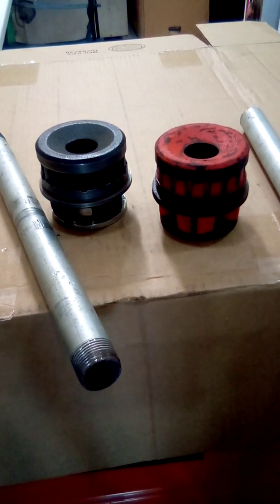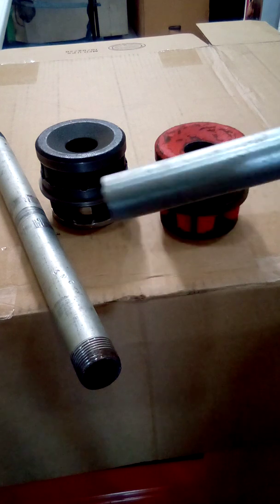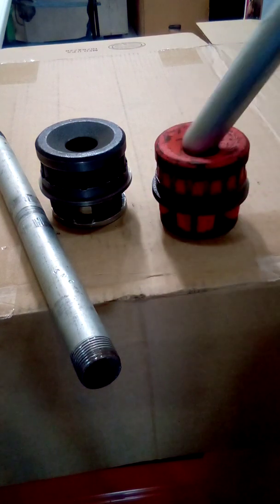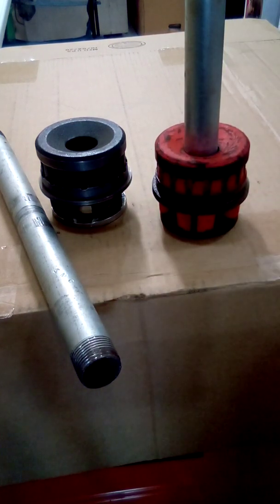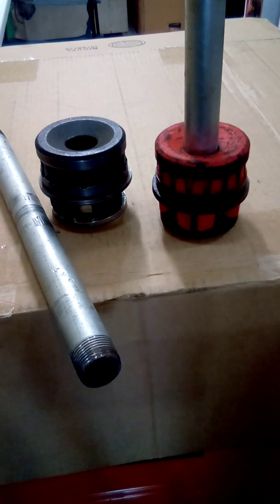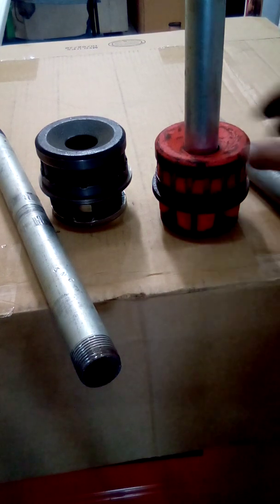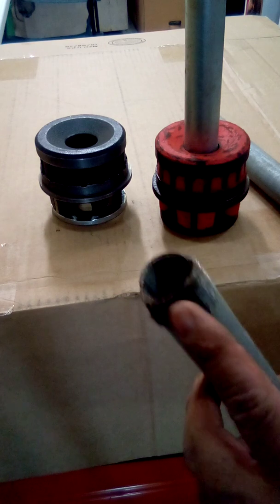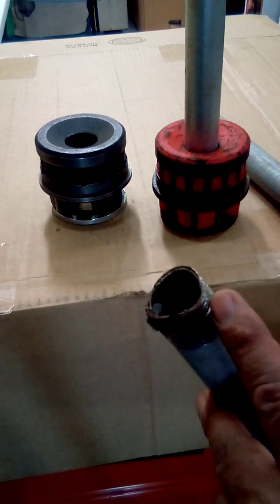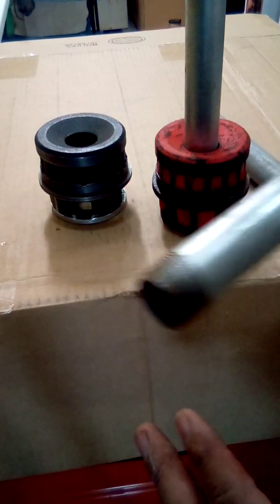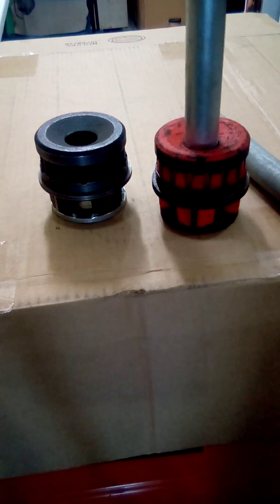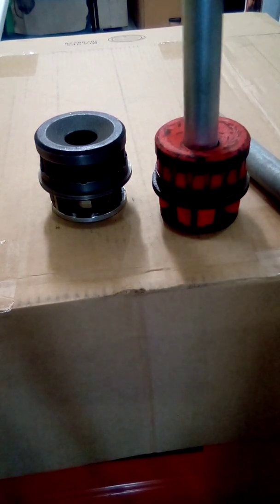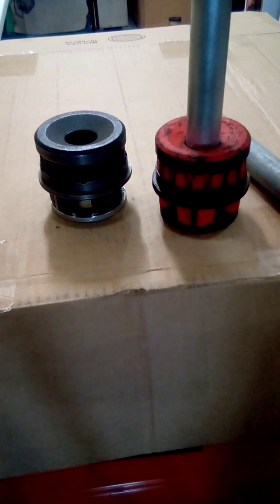On that job site we were threading IMC and we were using the rigid die, okay. So what's happening is it was chewing it up like this, collapsing it, okay.